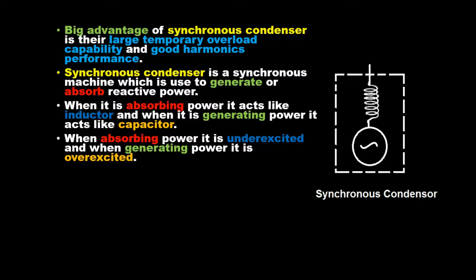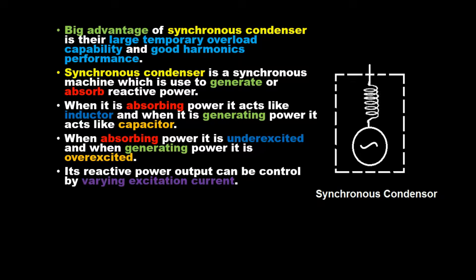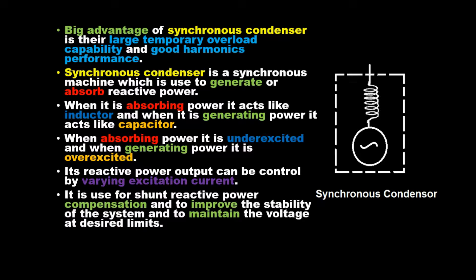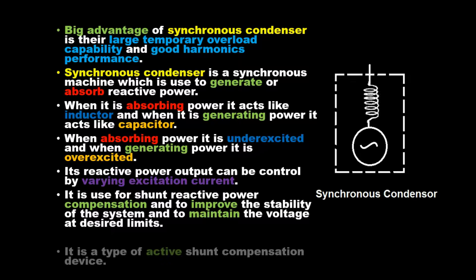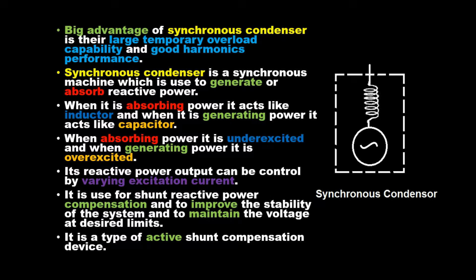Its reactive power output can be controlled by varying the excitation current. It is used for shunt reactive power compensation, to improve the stability of the system, and to maintain voltage at desired limits. It is a type of active shunt compensation device.